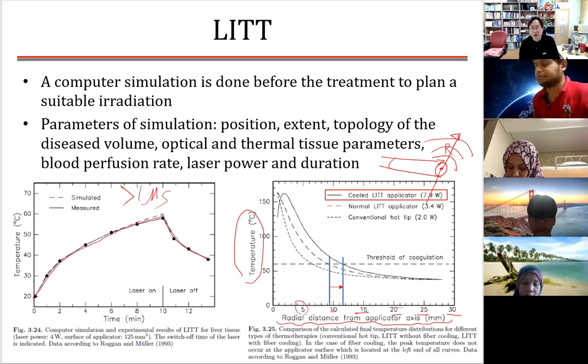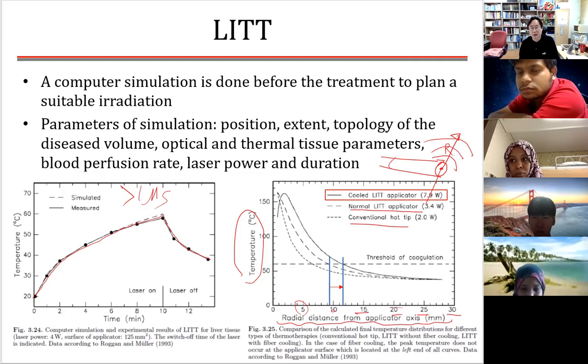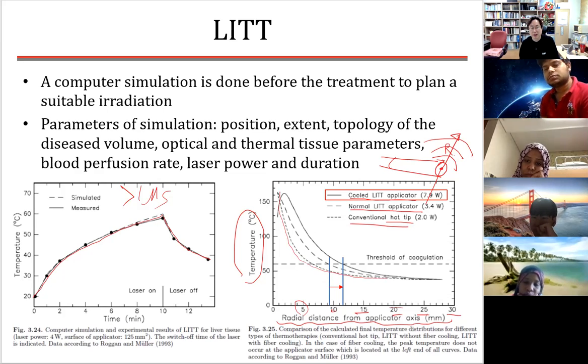When you look at the temperature change along this radial distance, there are three examples here. The first one is the conventional hot tip, the second is the normal LITT applicator, and the third is the cooled LITT applicator. Conventional hot tip means you have a kind of tungsten wire generating the heat, and you measure temperature along this R direction. You can see that it goes down immediately. The threshold for coagulation is 60 degrees Celsius, which is about 7 millimeter. If you are using the normal LITT applicator, that's a little bit longer, about 9 millimeter.